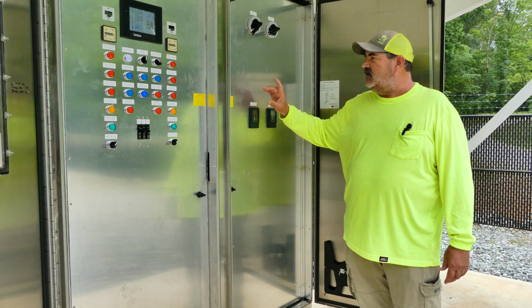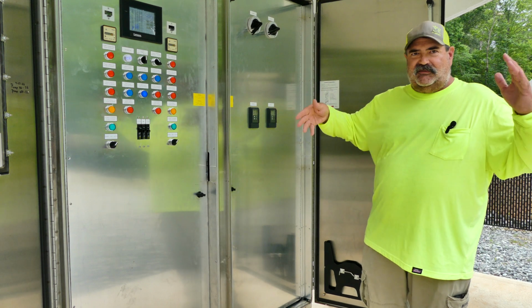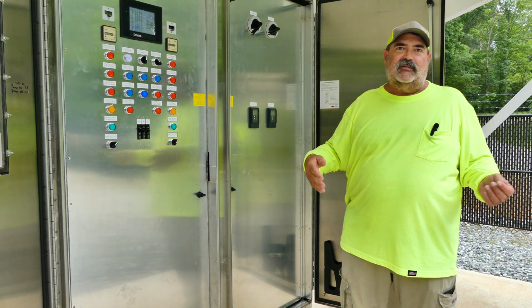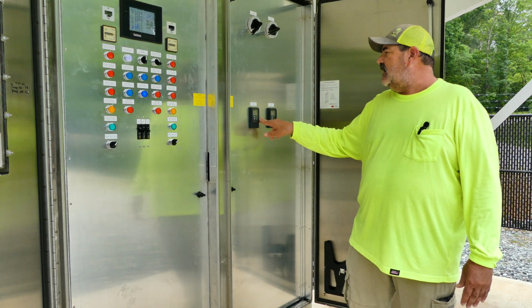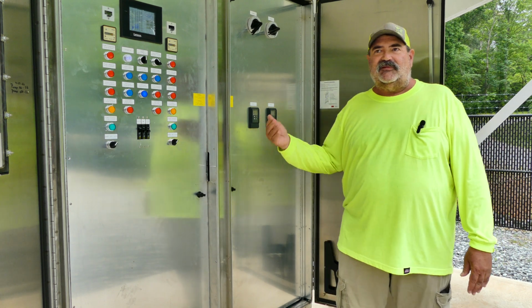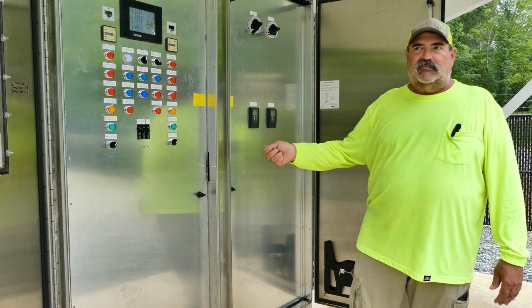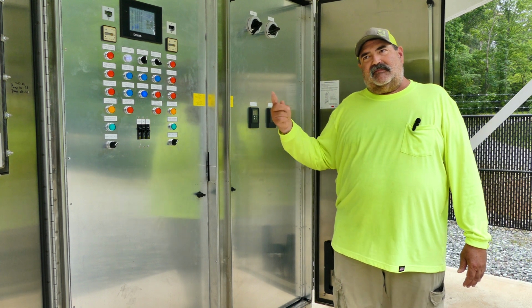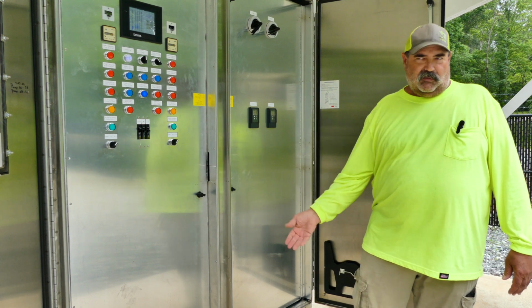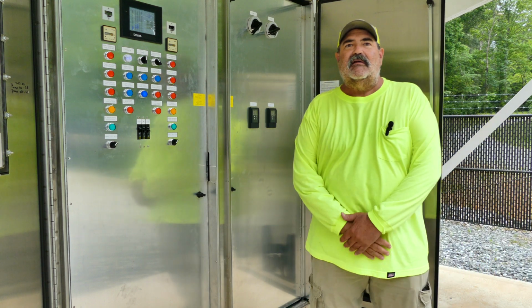Amps will be between a certain range, full load amps versus zero. And we can look at these amps and tell if we have a problem with the pump, such as something getting lodged in it, it will draw more amps. If this impeller comes loose, it'll draw a whole lot less amps, things like that.